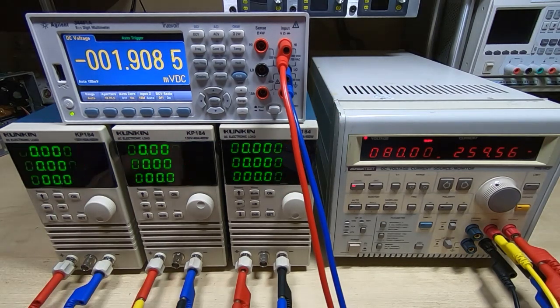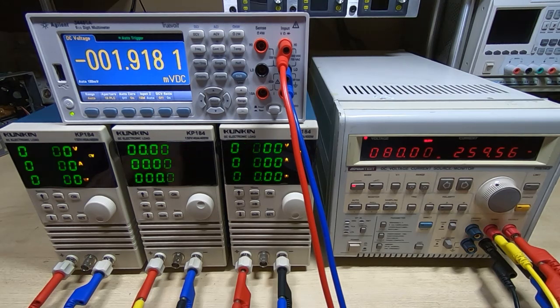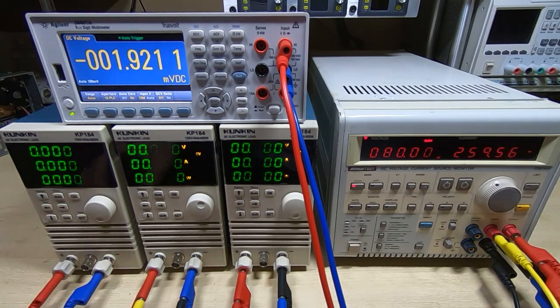These have now all been running for about two hours so they're nicely settled down. You need to give them plenty of time to settle of course, otherwise they'll just drift after you've completed the calibration and you won't have really gained anything.